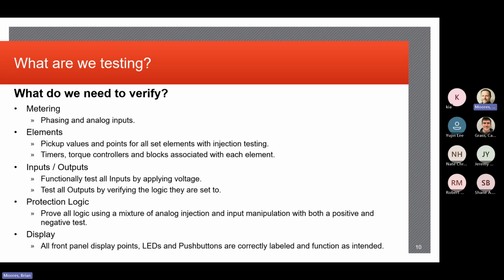All right, torque controllers. What's torque control? You guys talk about that at all? Basically, we'll call it internal permission. So you set up some of these equations that say you want this function or this element only to work for certain, maybe it's a range of an angle, or maybe there's a piece of logic in there that's only working when this function's enabled. Those sorts of things. So those are kind of another logic. Timers. So there's so much involved, and I'm not getting deep into those relay settings, but it's important that we validate each one of those settings that's enabled.